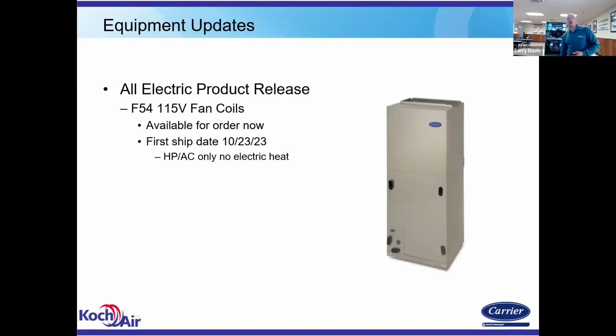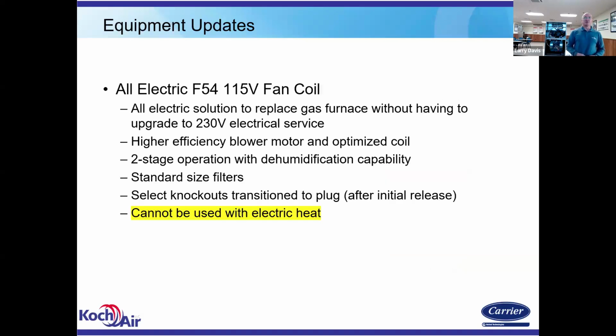This is a product I want to spend a minute talking about. If you have an application where maybe you have boiler heat or hydronic heat, and you're getting rid of a gas furnace and going all electric or something, we have an air handler that's factory installed with a 110 volt motor and 110 volt controls. This is available in 2 to 5 tons. Same thing about the knockout plugs. It's 2-stage compatible and also handles dehumidification, but obviously you can't put electric heat in it. Can't hook a toaster up to it. Okay, and it's non-communicating.